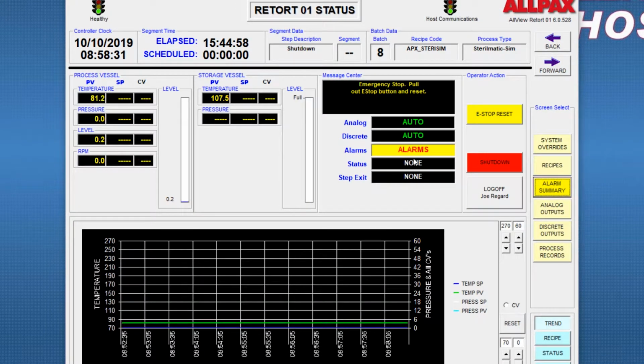Directly underneath that is the status. The status refers to the integrity of your current batch. So when you're running a process, if for instance the boiler goes out and you lose steam, or maybe a valve breaks and the machine overflows with water, you get more water in the machine than the process would allow, the process would be considered deviated, and that just means your recipe didn't go as intended. Either there was a drop in temperature, there was too much water in the vessel, something happened to basically corrupt your product, and it will consider the batch deviated.